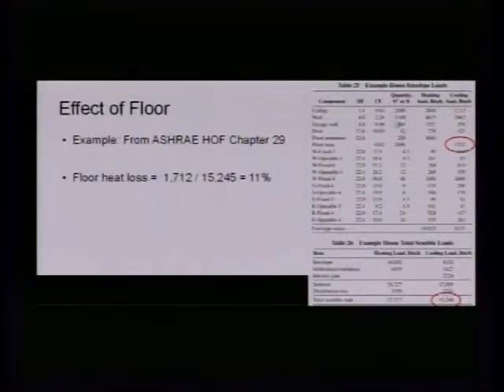But for a single floor, it should be the same. And guess what? This is the table for the house. This is the floor heat loss right there, and this is the peak cooling load. And we are talking about 11%, right at the safety factor that is recommended by ASHRAE.